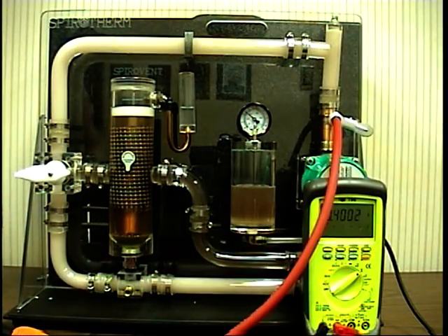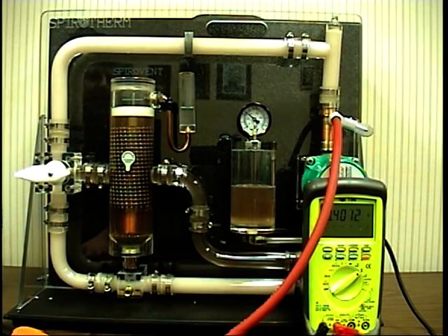Now we'll take a look at the system. And one thing we can really see, you don't have the big air bubbles anymore. The glycol has changed to a foam state. And basically, the system doesn't sound that bad compared to the water system, where you can really hear the air going through the pump. But you can see the foam is really just pure foam. And foam is really a true insulator within the system itself. Really cuts back on the heat transfer within the system.